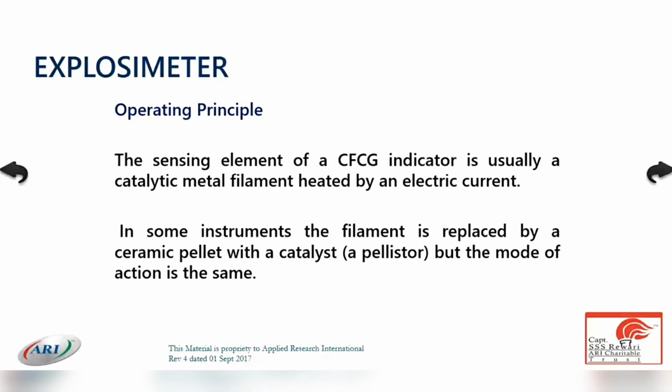The sensor can get damaged. There is a very high chance of sensor damage, for many reasons. Maybe because some other toxic gases are around, the sensor gets damaged. If you use that same explosive sensor in an inerted state, or the tank scope in a high oxygen state, the sensor can get damaged, but not so much. Oxygen sensors are getting damaged more than the explosive meter and the tank scope. Am I right? Very often you are changing oxygen sensors. Most of the time you are changing oxygen sensors. Very rarely do you change these other sensors. They are very strong, and damage to them is hardly seen.